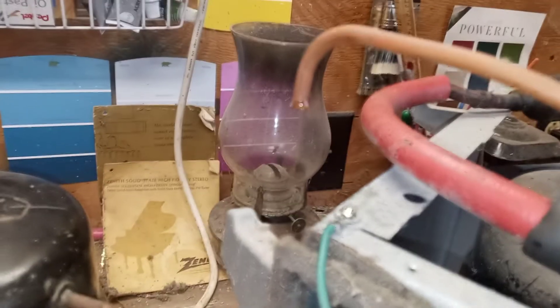I don't want to run it too long — she's throwing a little bit of oil out, which is common. Let's not run it too long. The oil is good and clear, so that compressor is good.